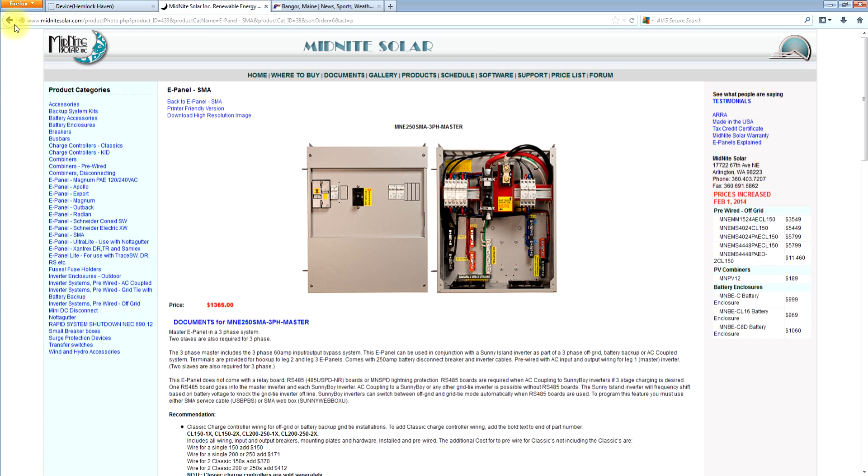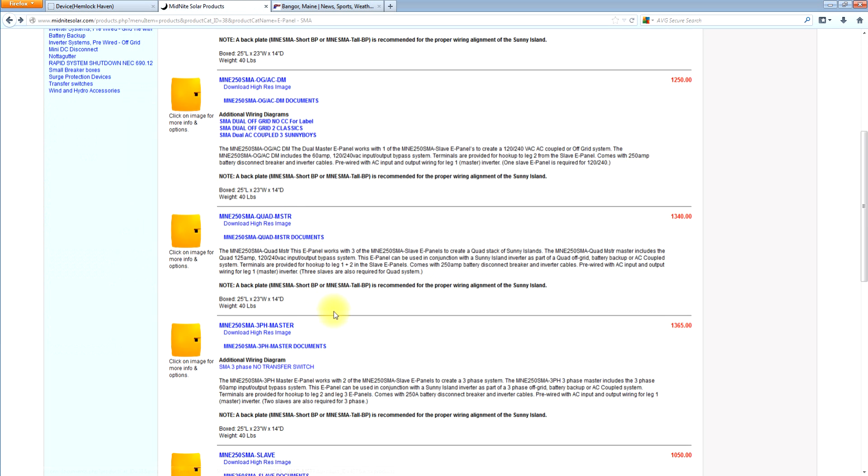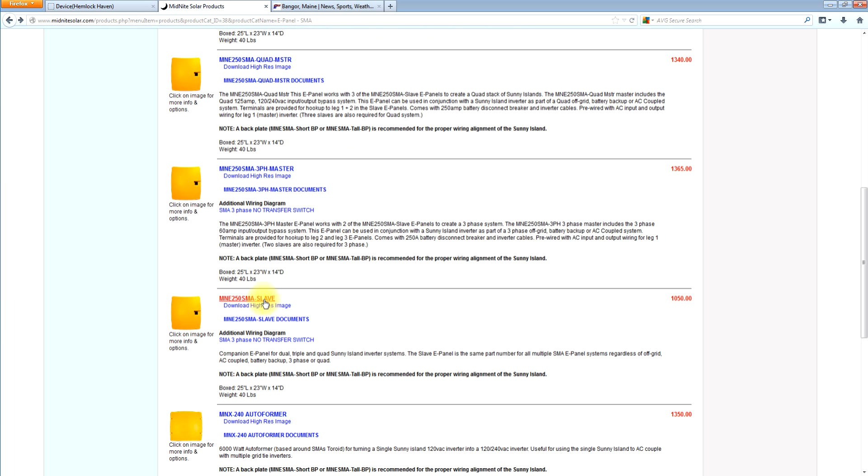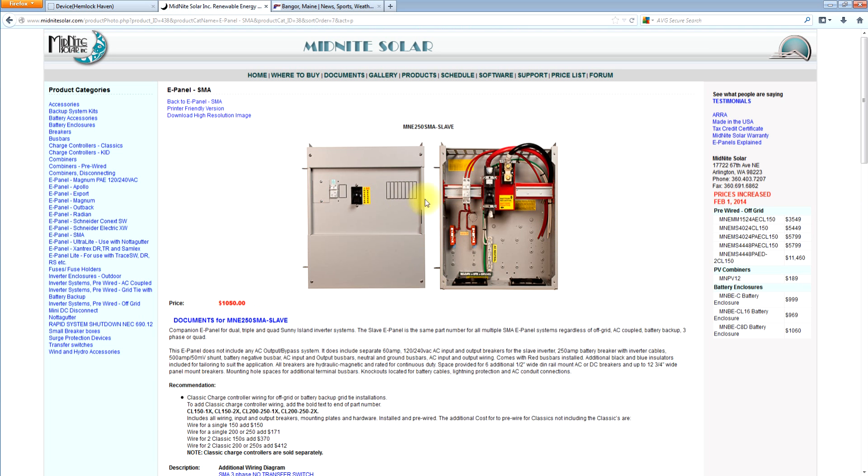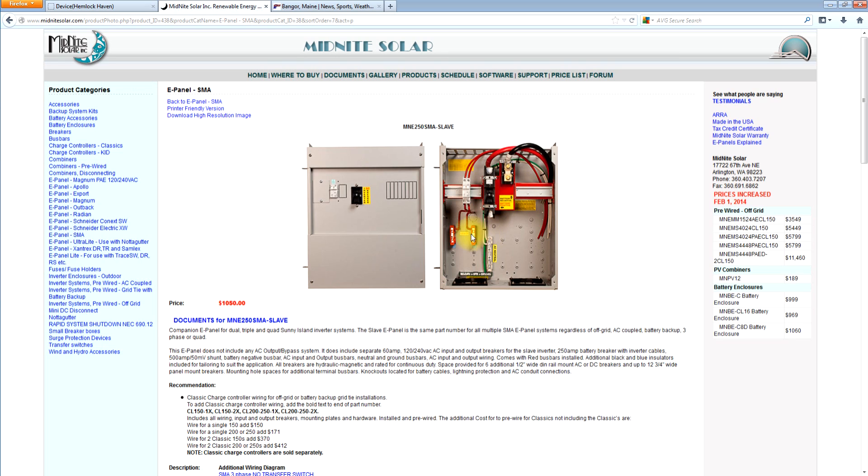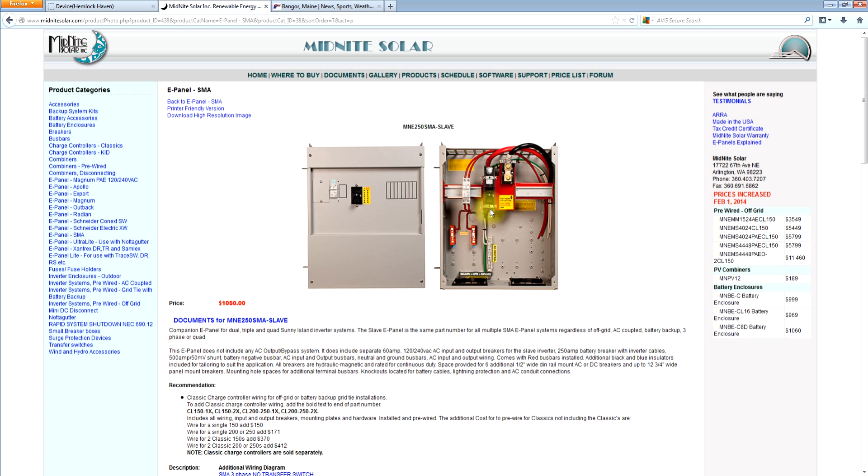So now let's go look at the slave e-panels. So as you can see here, the slave e-panel is pretty empty. It's just what it says, it is for the slave Sunny Islands. So it's for the second, third, or fourth Sunny Island. And it does come with a bunch of different insulators. You can change the colors of this depending on whether it's three phase or if it needs to be black for a quad stack and it's still L1. So essentially it's just an e-panel for each one of the slave inverters. And then it would just get wired over to the master.